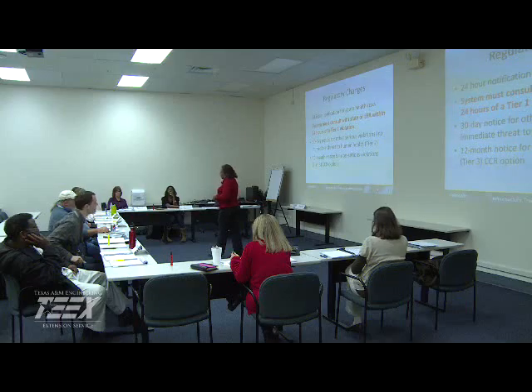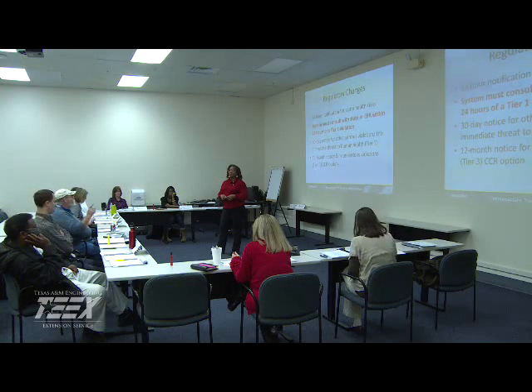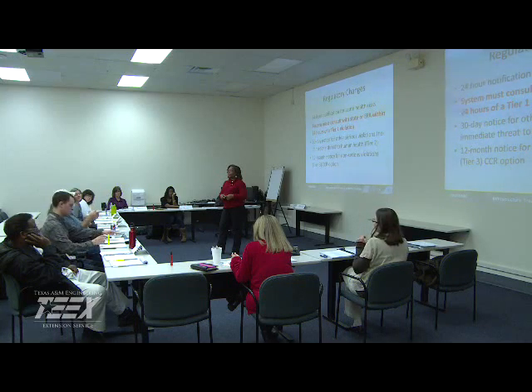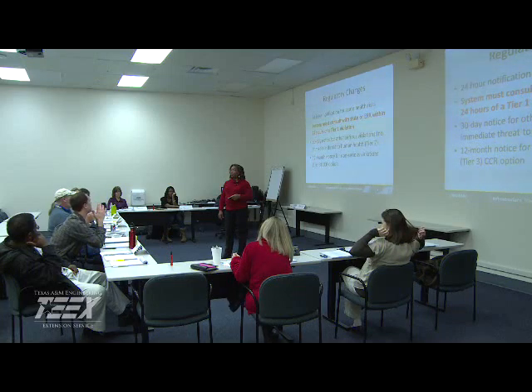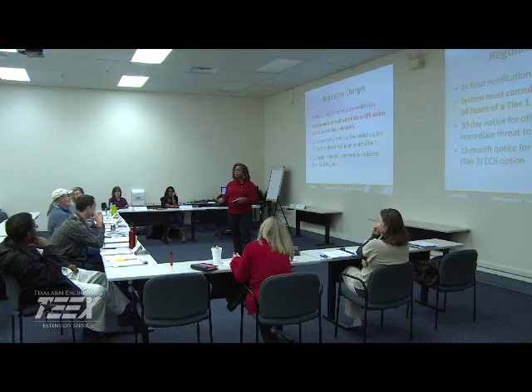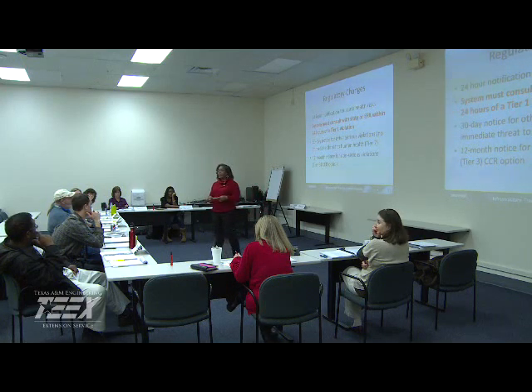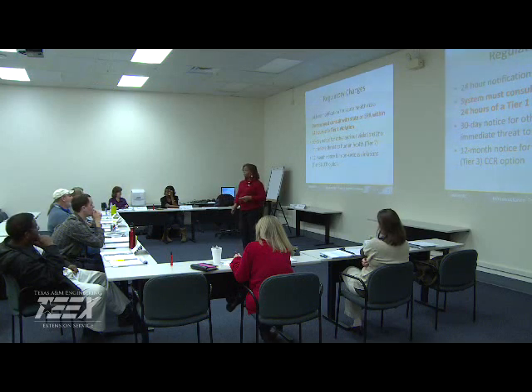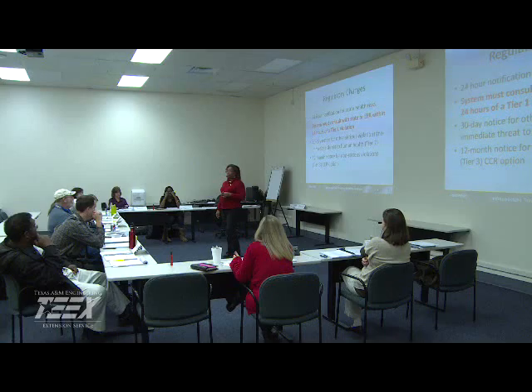When we get the first positive E. coli hit, do we respond to the first hit, or do we wait for confirmation? Wait until the confirmation. Even though we're in panic mode, the repeat samples are going to take about 24 hours to collect, but by the time you test them you're two or three days down the road. We've had situations where the first one is dirty and the rest are okay. We go back to the state to validate, because that first result may not be representative — it could be an operator sampling error, perhaps a screen on the sink or something. Sample error is a very small chance — less than 5% — that actually causes your problems.